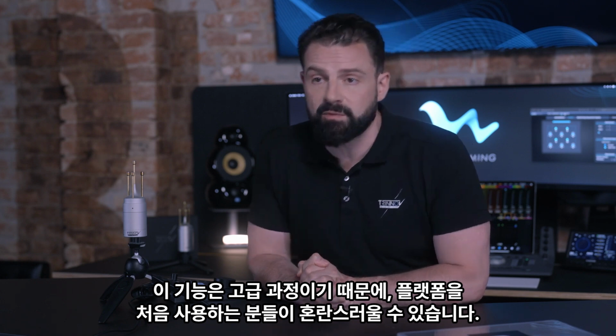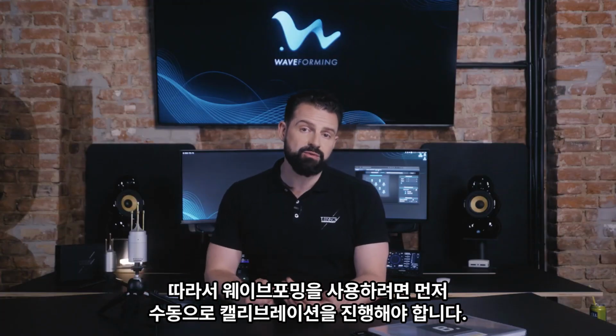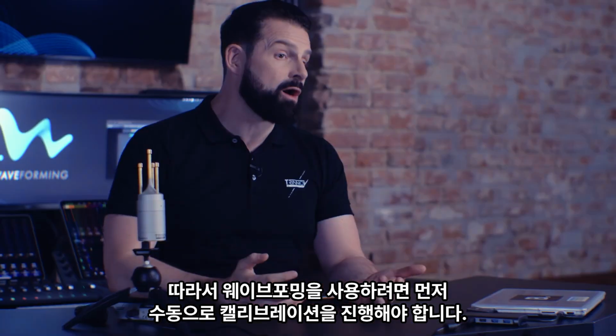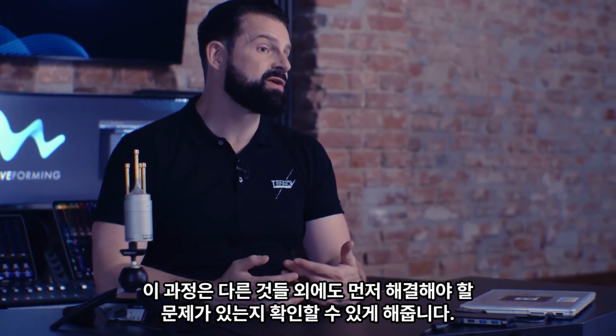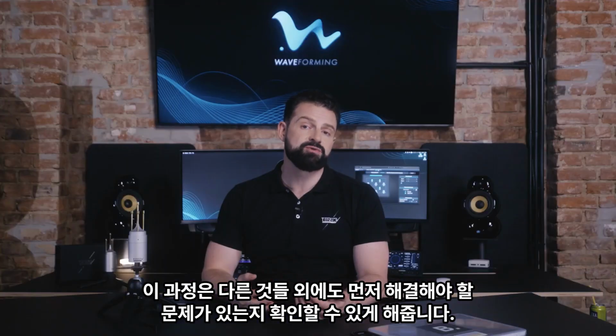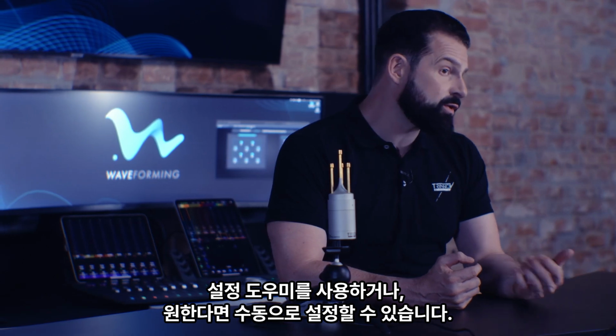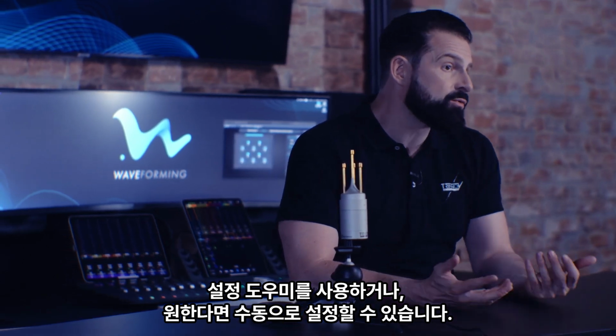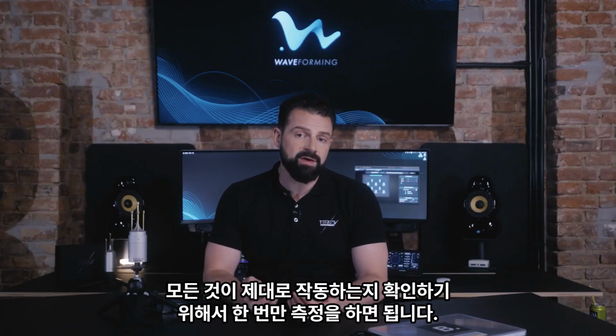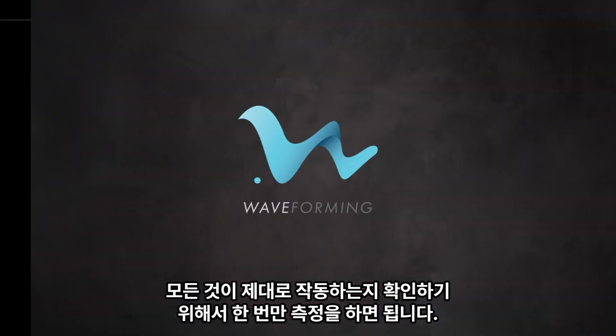So first, you will need to do a manual calibration to use waveforming. Among other things, this lets you see if there are any obvious problems that need to be addressed first. You can use either the setup wizard or do it manually as you prefer, and need only the single reference measurement to ensure everything is okay.